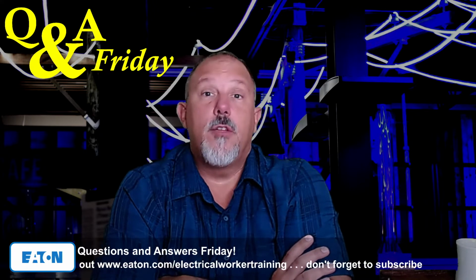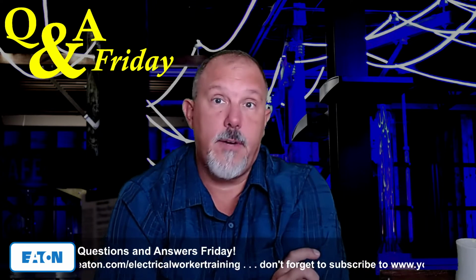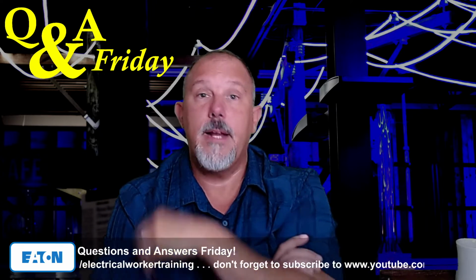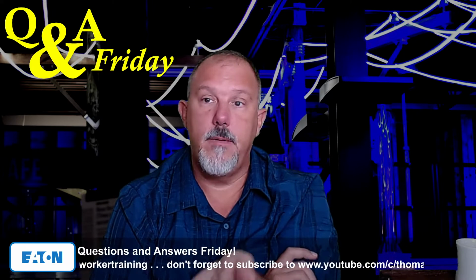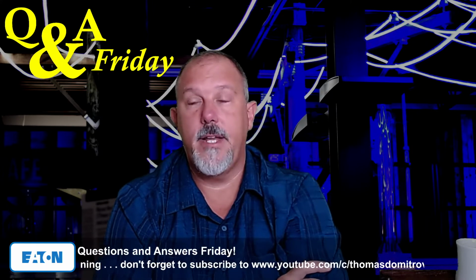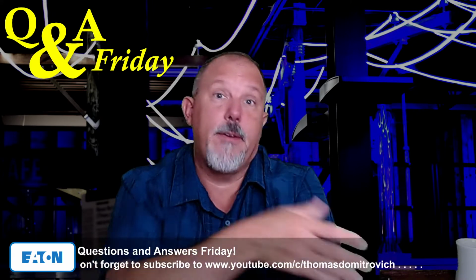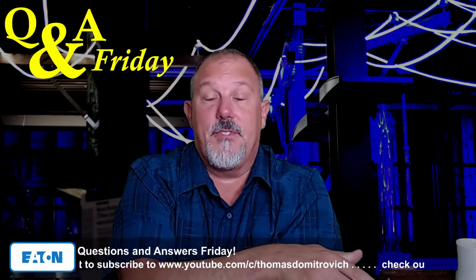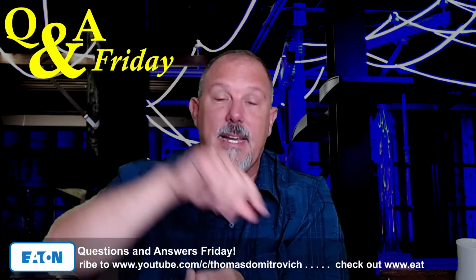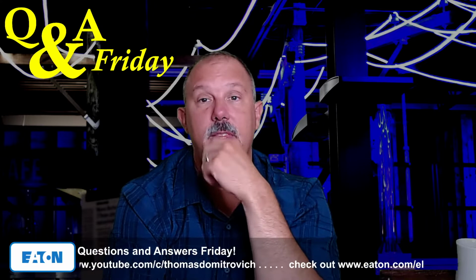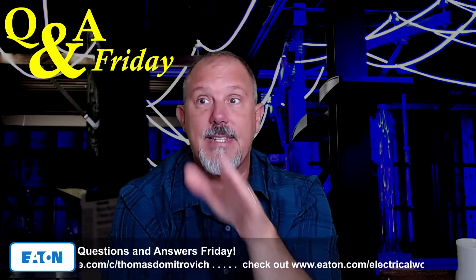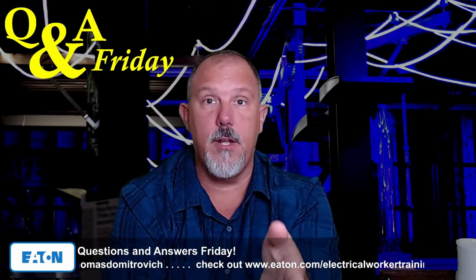So I have that 1200 amp breaker that can carry 1200 amps, and I adjust it down to something lower. I could carry up to 1200 amps on that, and I'm actually carrying something less, 80% less. Right? So I'm adjusting the long time pickup down, so the overcurrent device can handle more than what I'm putting on it.